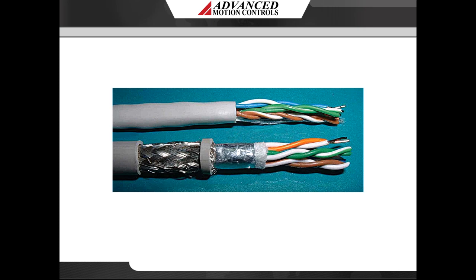Cables are susceptible to EMI, both as a source acting as an antenna and as a receiver picking up noise radiated from other equipment. Cable shielding is an effective way to protect data against EMI, reduce emissions and increase robustness. Twisted pairs of wires are also quite effective in reducing magnetic pickup because the enclosed area is small and the signals induced in successive twists cancel.